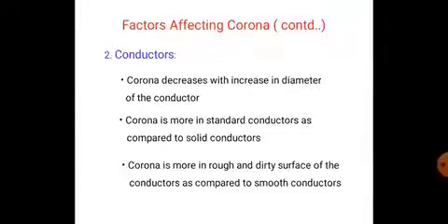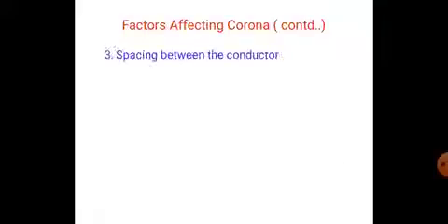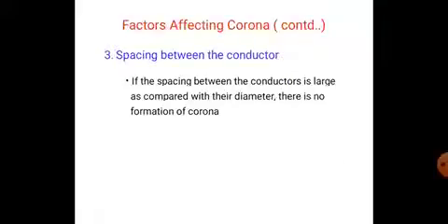Corona is more in rough and dirty surface of the conductor as compared to smooth conductors. Spacing between the conductors: if the spacing between the conductors is large as compared with their diameter, there is no formation of corona. The spacing between the conductors should be large as compared with the diameter.